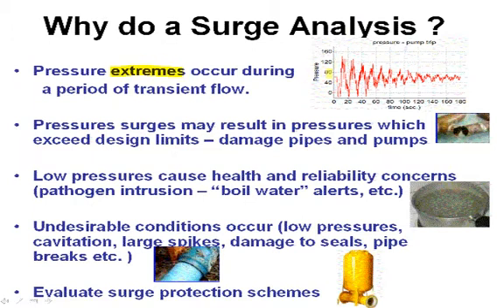Here, for example, is the pressure following a pump trip. Initially the pressure is here. Finally the pressure is here. But in between, it comes down and actually goes below atmospheric pressure, then spikes up to about twice the normal pressure.